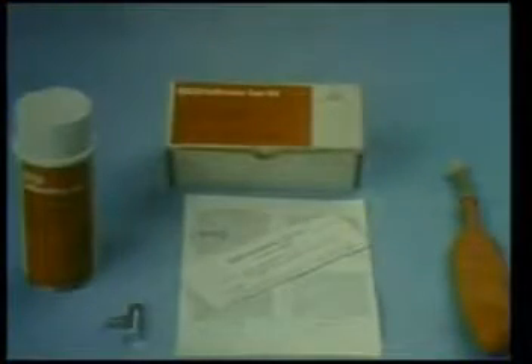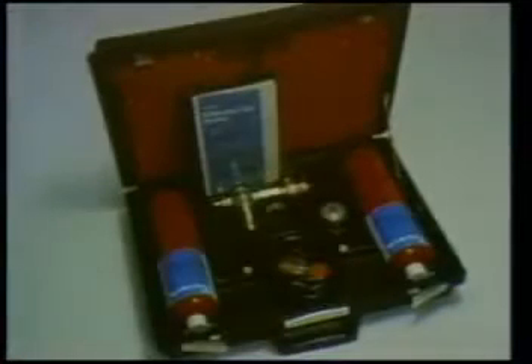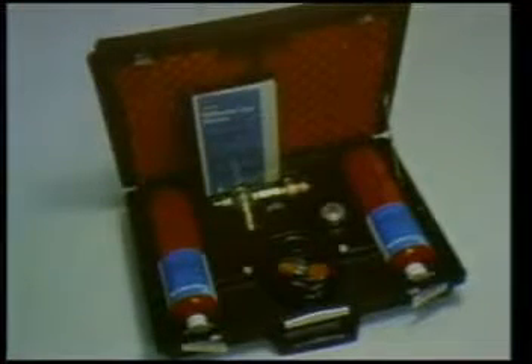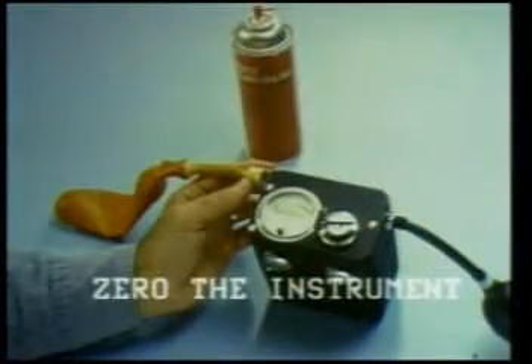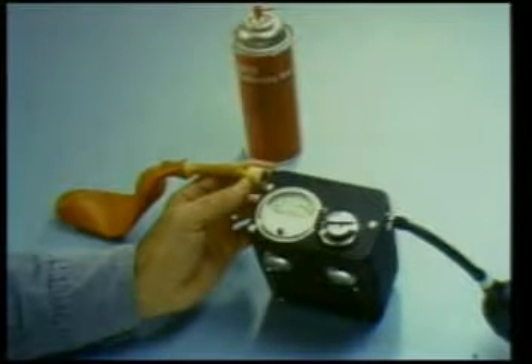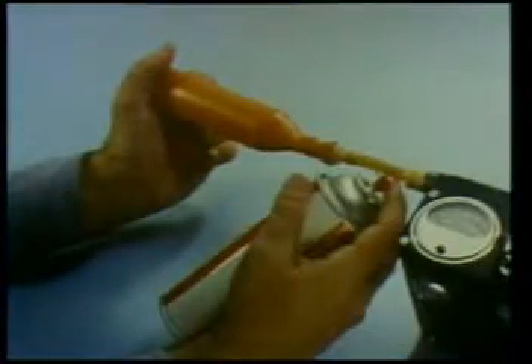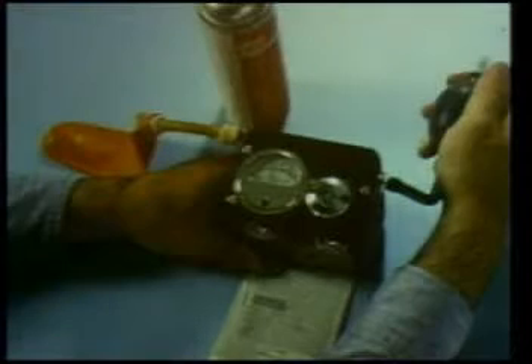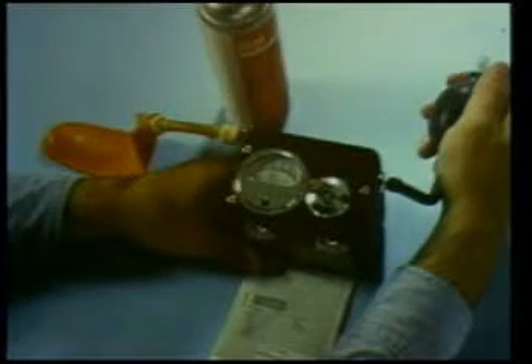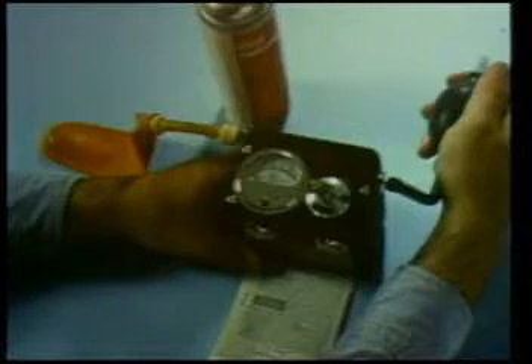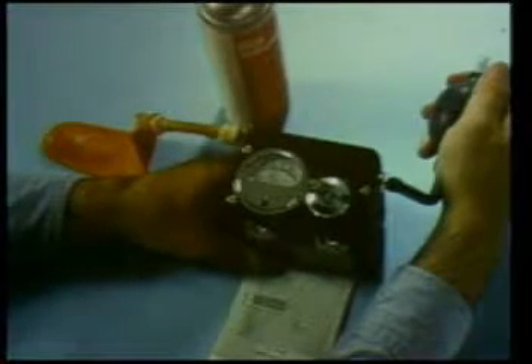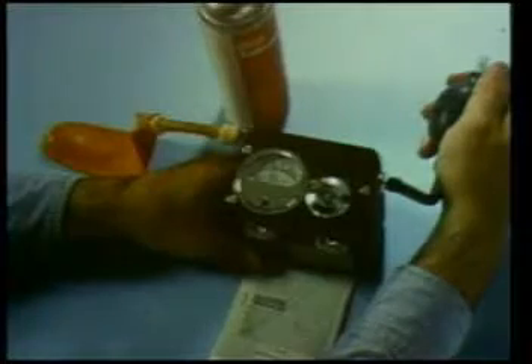The calibration may be checked in the field with a portable test kit or check kit containing a known concentration of methane in air. The first step in the calibration check process is to zero the instrument. If you're using the calibration test kit, connect the bladder assembly to the inlet fitting of the instrument. Insert the needle of the aerosol can of calibrating gas into the tubing, not the bladder, and press the button to inflate the bladder. Squeeze the aspirator bulb to draw the calibrating gas from the bladder into the instrument. Compare the upscale meter reading with the response curve for the explosimeter Model 2A furnished with the test kit.